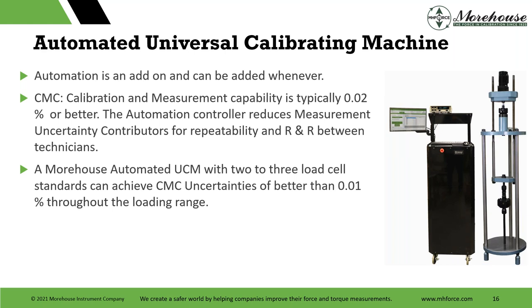When I talk to people, I usually ask, what is your workload? If somebody says I have 100 of these 10,000 pound load cells that I anticipate coming in, or 200 that I calibrate over a year, I might say it's probably your best bet to buy a 10,000 pound reference, because then you can do those. Do not try to split those 10,000 pound load cells between a 25K reference and a 5,000 pound reference, because then your technician's going to be switching standards 200 times a year, whereas if they bought a 10,000 pound reference, they may not have to. So hopefully that makes sense. That's coherent to people.